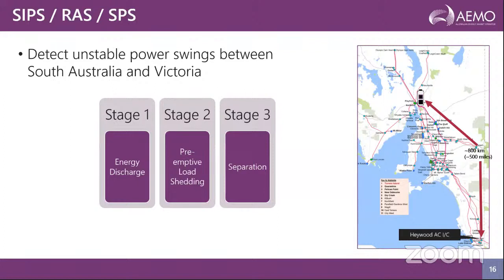The figure on the right is how the South Australian power system looks like. Following a detection, it takes action if it detects the loss of synchronism between South Australia and the rest of the NEM regions. It has three stages. The stage one is where it makes use of batteries. Stage two is a preemptive disconnection of load to defer separation of South Australia. And the stage three is actually opening up the border and forming an island.